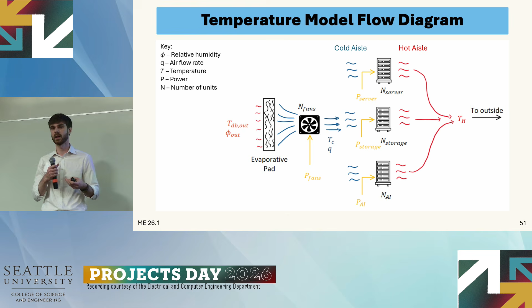And the purpose of this model is to check if that temperature is above or below 120 degrees Fahrenheit. And if it's above 120 degrees Fahrenheit, the model will report that the system is overheating. And the reasoning behind this is just a standard for how the maximum temperature of that hot aisle should be. The assumptions we make are that this evaporative pad is bringing our air up to 85% relative humidity.